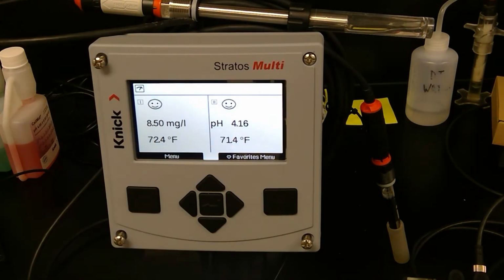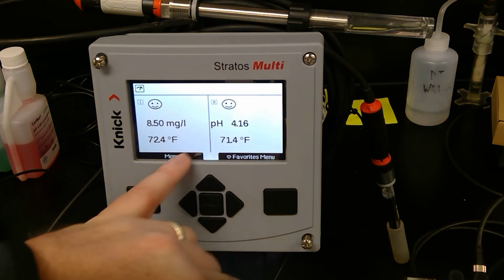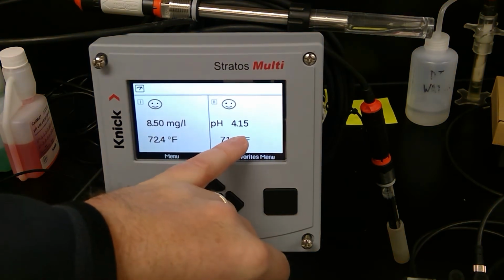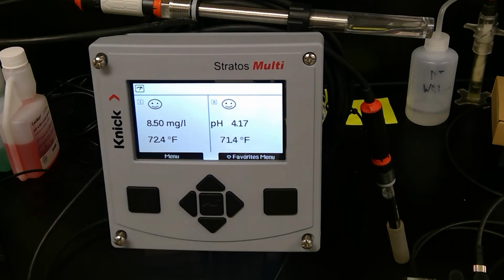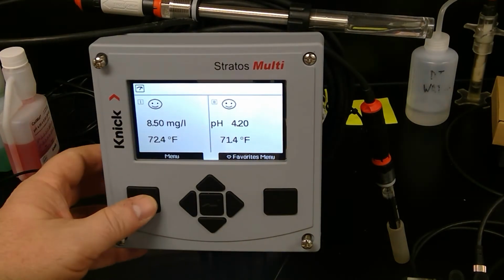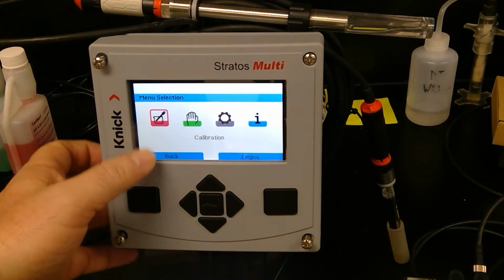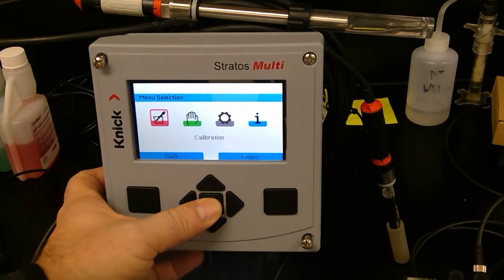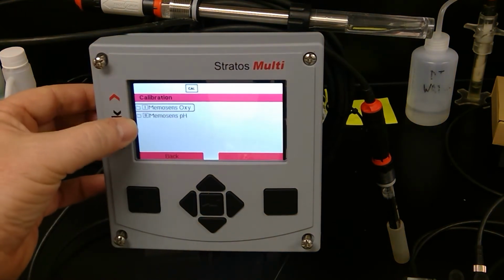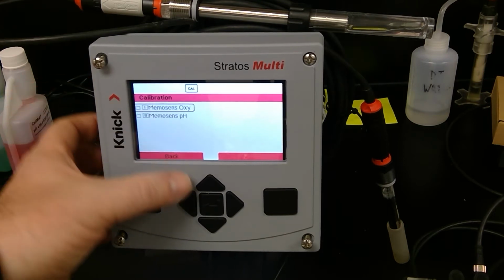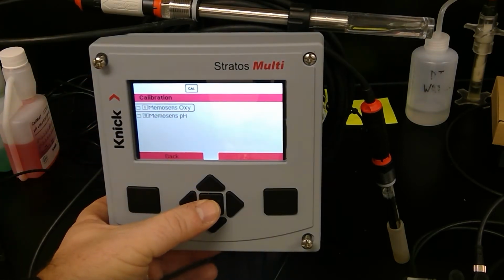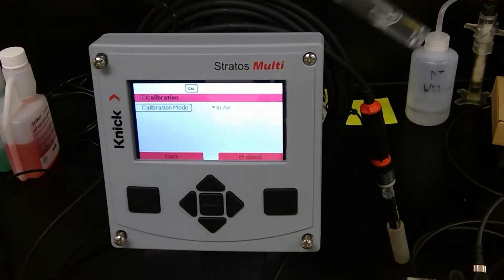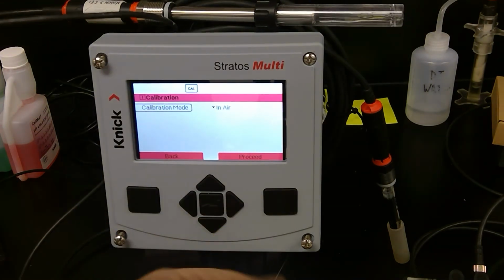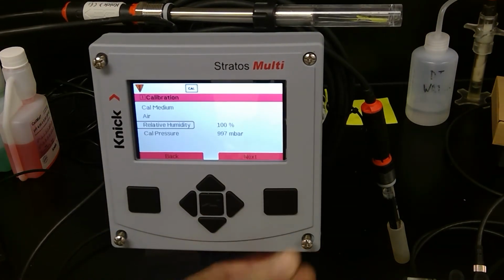Now this is a Stratos Multi that we're doing the calibration on. You'll notice this is a dual channel version. We've got pH here on the one side. We have dissolved oxygen on the other, which is sensor 1. I go into menu and you'll see here that I've got calibration as my first choice. And then I need to tell it which channel. In this case, I want oxygen, MemoSens oxygen for channel 1 or sensor 1. And I'm going to do an air calibration. All right, it's in the calibration beaker, so I want to go ahead and hit proceed.